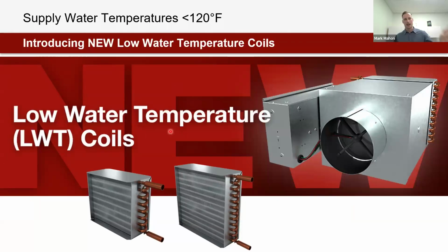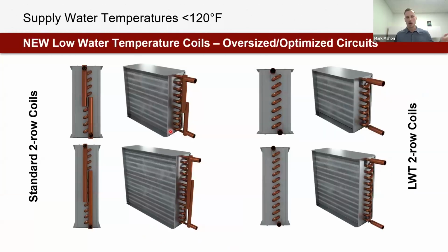And of course, the next natural question is, what is a low water temperature coil and how does it work? So I want to look at the scope here of a standard 2-row coil compared to a low water temperature coil. This is an even more fun exercise if we have the actual samples in front of us. So I've drawn a few graphics on screen to discuss this. The first thing I want to note is this is automatically and always an oversized coil. There is no point in doing it with a standard small commodity sized coil. To really fully leverage the capabilities of this new option, the coil needed to get bigger. So oversized casings are inherently the option that we're recommending here. But the other big piece is the coil circuitry.